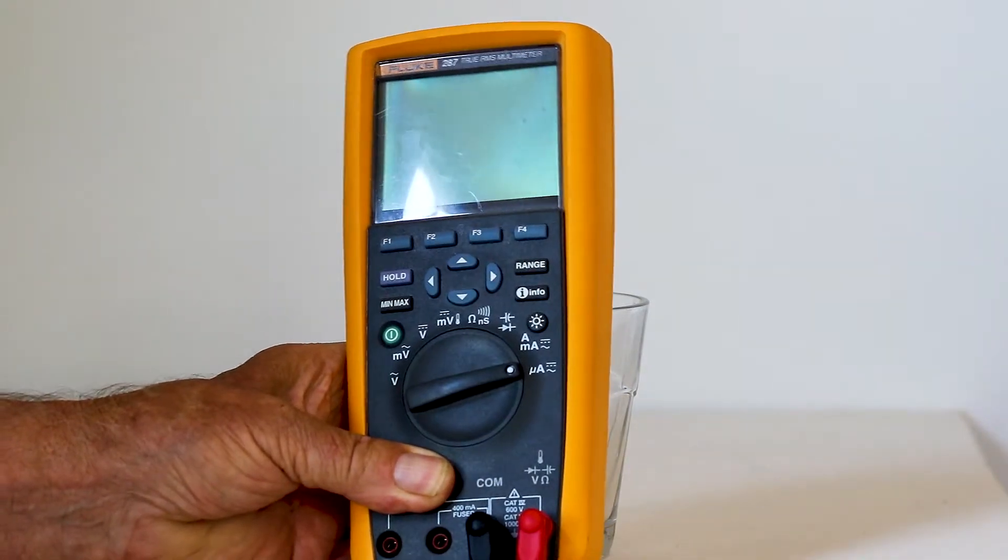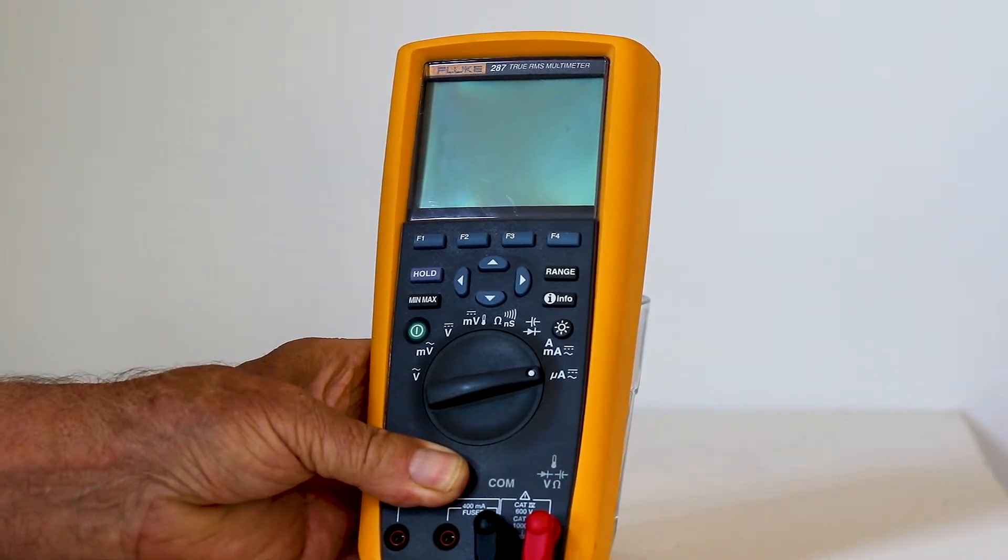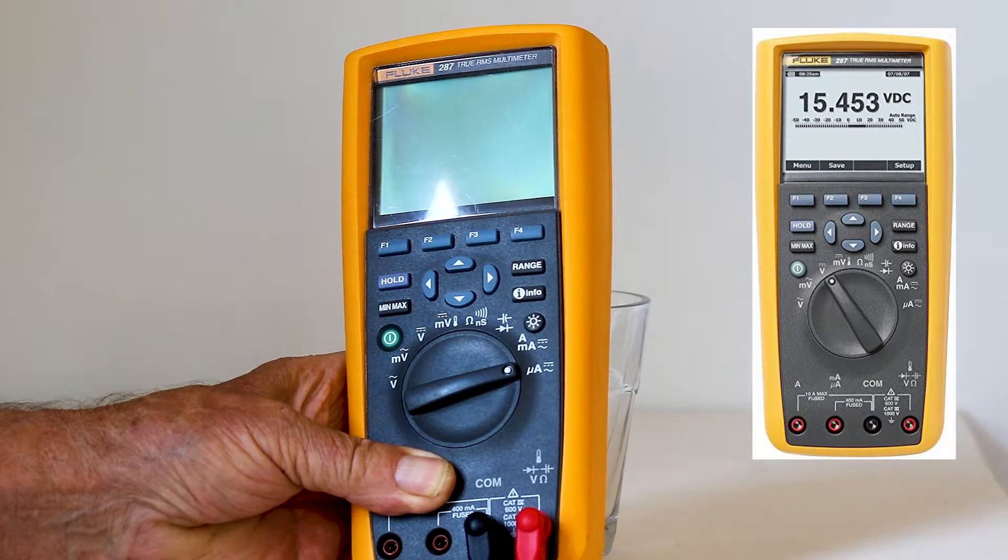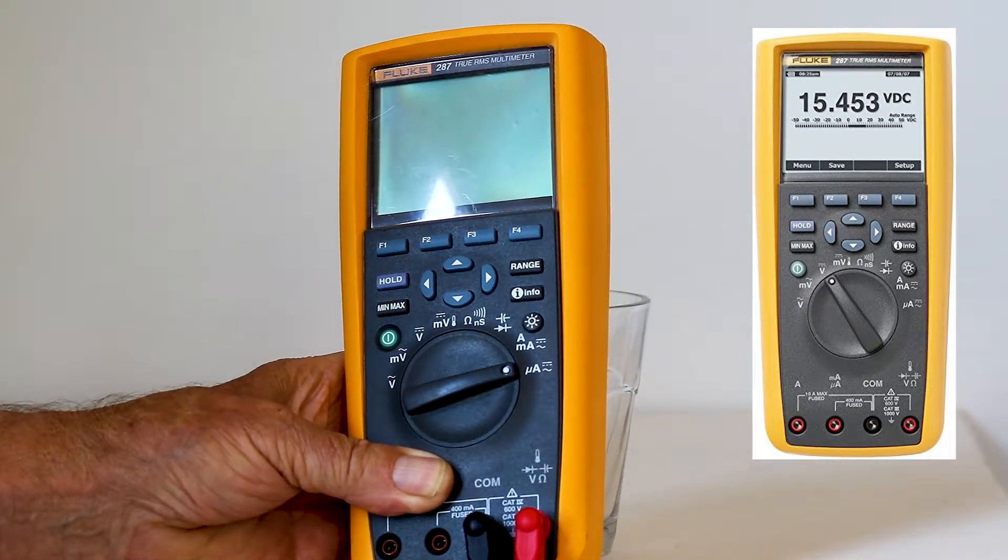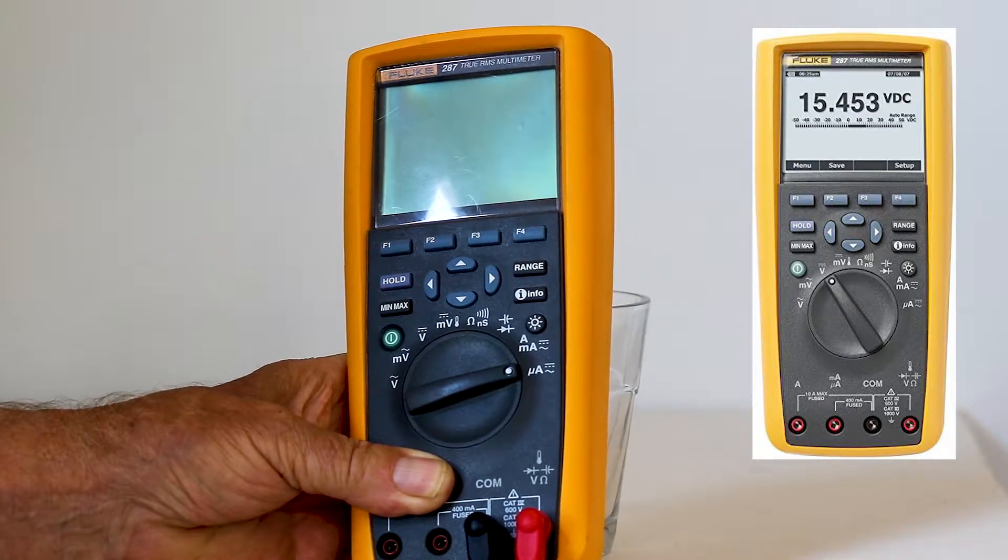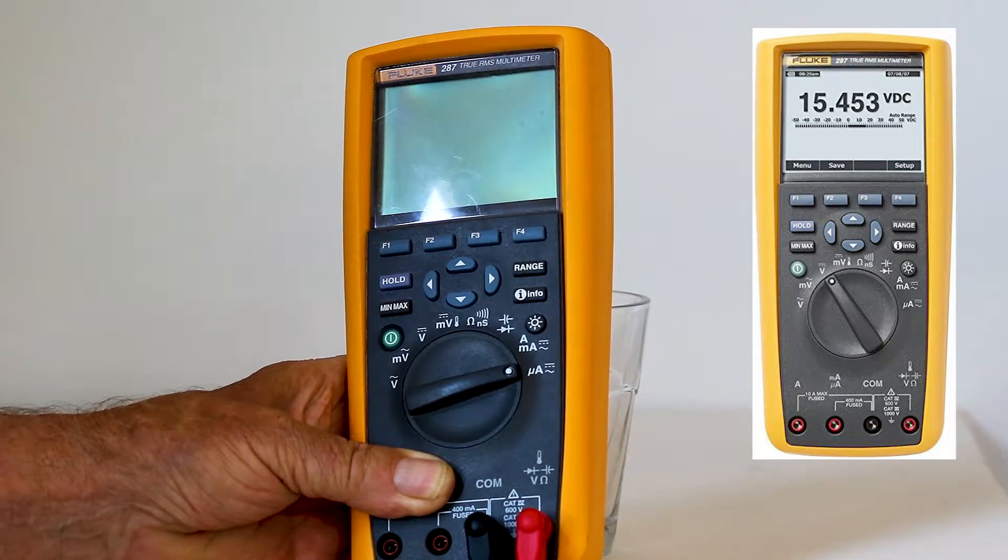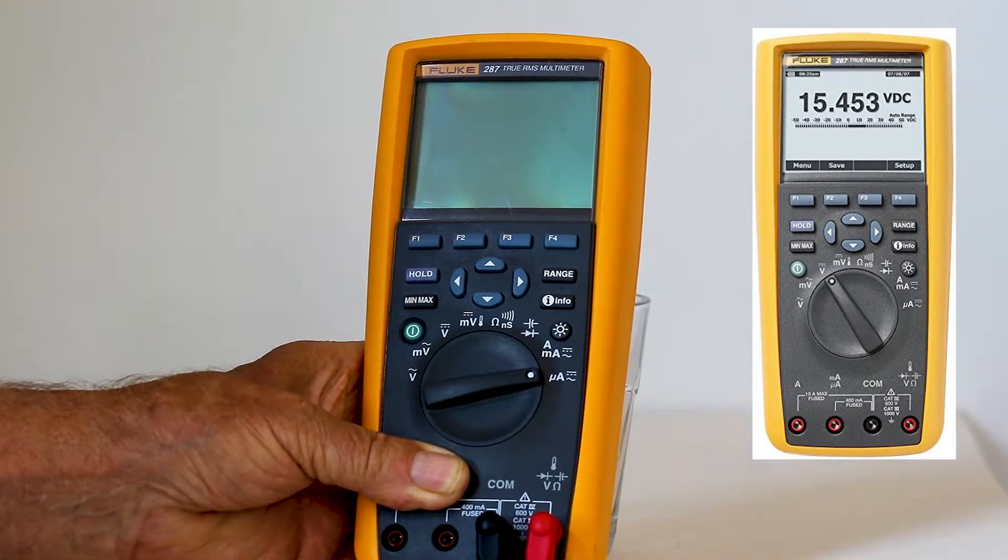The classic Fluke 287 true RMS multimeter sets the standard for all such instruments. It is equipped with a seemingly endless array of advanced features. The extraordinarily clear display and simple user-friendly interface make it a joy to use. The CAT 600 volt rating in CAT 4 locations and 1,000 volt rating in CAT 3 locations means that this meter is good for three-phase 480 volt systems.